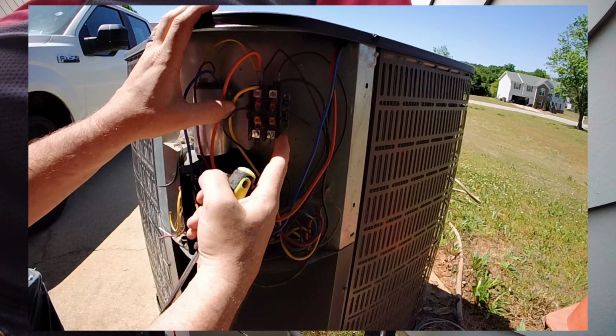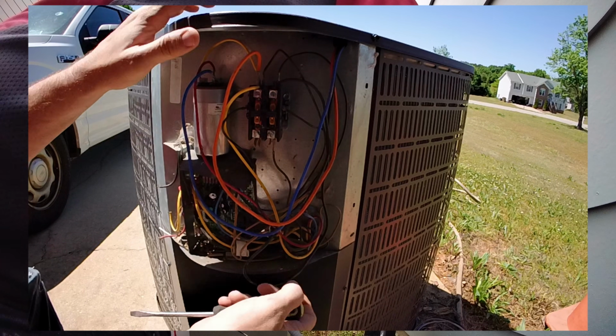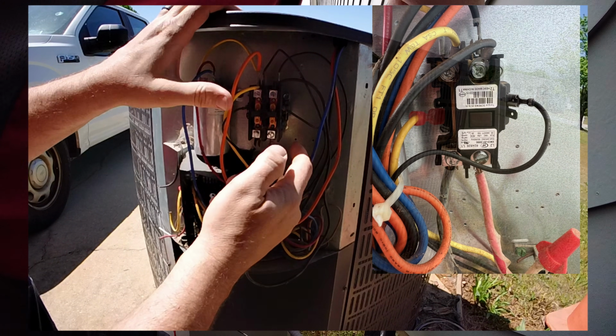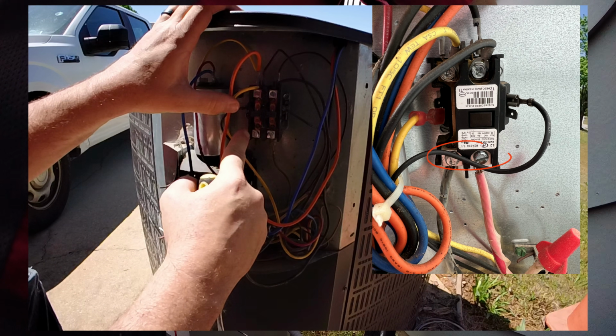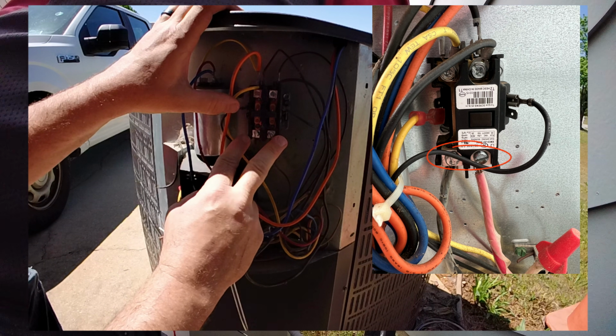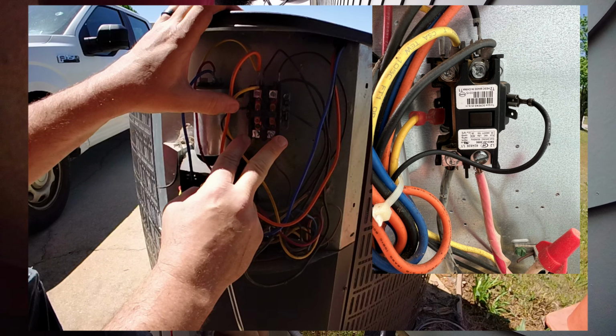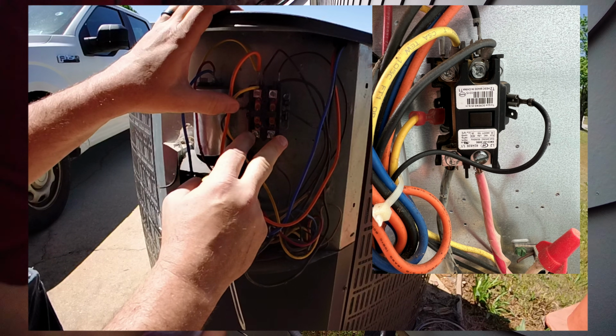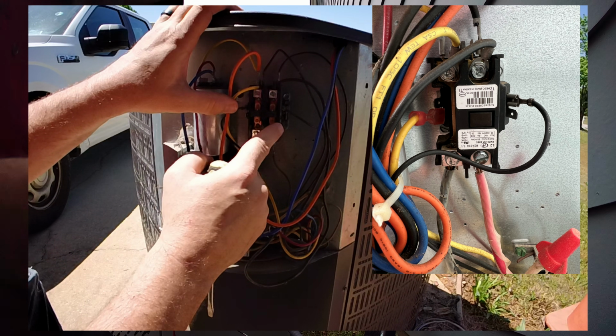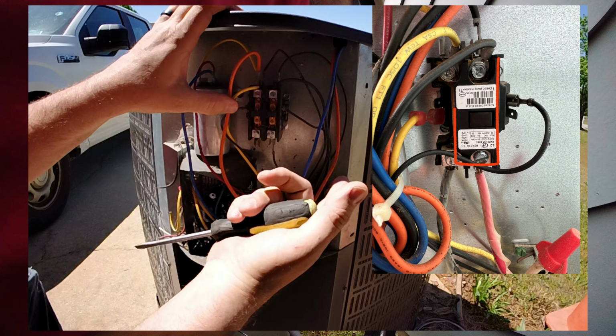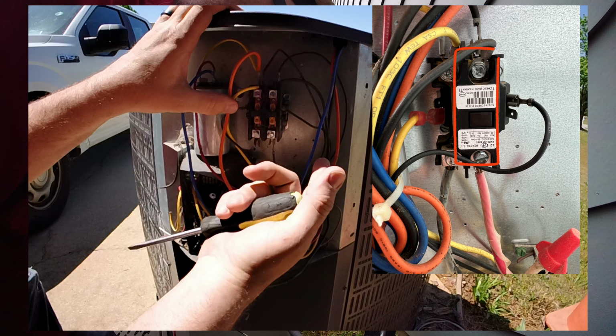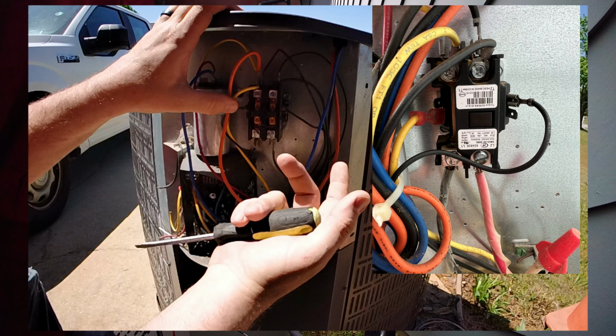But these guys work fairly simply. I kind of refer to it as a temperature actuated light switch if you consider this unit your light. So you have your high voltage connections, line 1 and line 2, connecting here at the bottom on this particular one, as well as the one we were working on. This one is a double pole contactor. We have 2 poles here. The one on the unit in the video is a single pole.